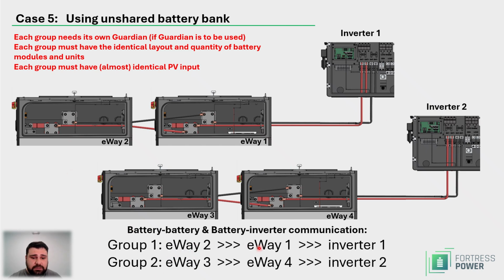Matter of fact, eWay 2 communicates to eWay 1, and eWay 1 communicates to inverter 1, and eWay 3 communicates to eWay 4, and then eWay 4 communicates to inverter 2. So there is no battery-to-battery communication between the groups. There's battery-to-battery communication within a group, and then each group communicates to its own inverter. So if Guardian is used, you use one Guardian per group. Each group must have the identical layout and quantity of battery modules and units. So if you have 4 eForces here, 1, 2, and 1, 2, you must have 4 eForces here as well. So 2 stacks. eWay 3 must have 2 eForces under it, and eWay 4 must have 2 eForces under it, if that's the case with eWay 1 and eWay 2.